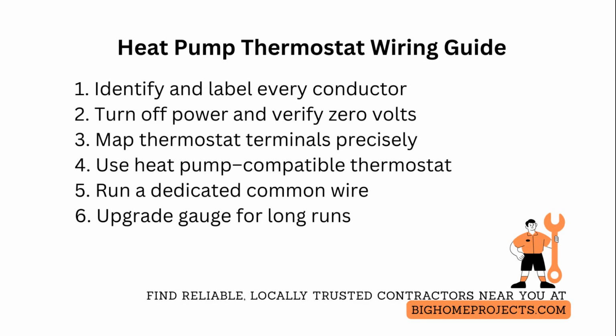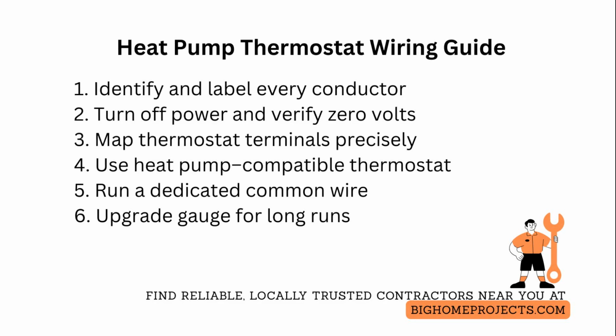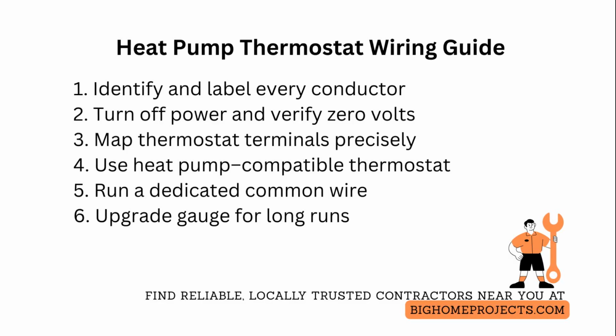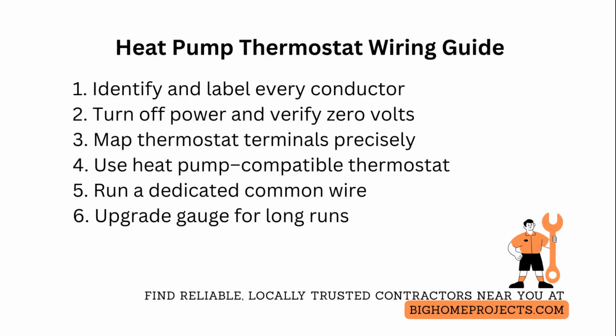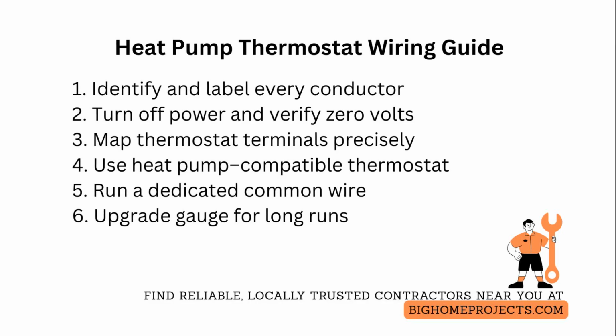Turn off power at the circuit breaker and confirm 0 volts with a multimeter before touching terminals. This prevents control board damage and personal injury. Map the thermostat terminals, common, heat, cool, fan, changeover or reversing valve, auxiliary or emergency heat, compressor stages, and defrost. Match colors, but always trace each wire if colors are non-standard.